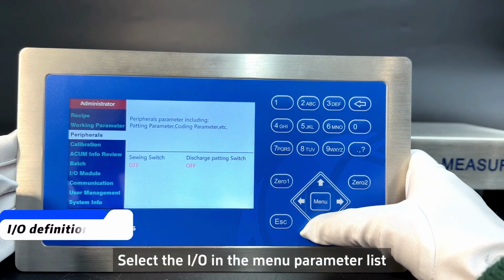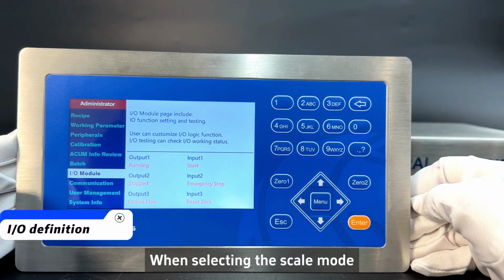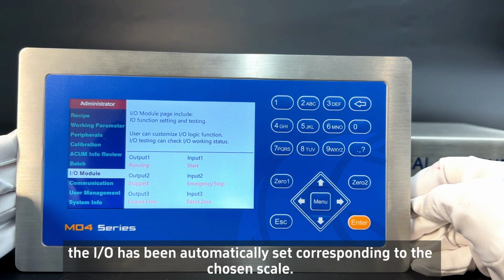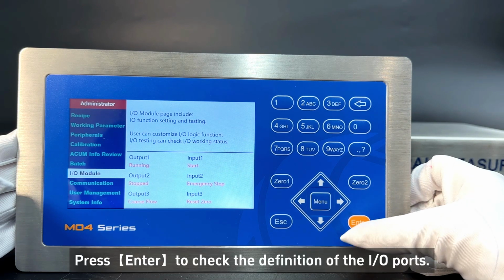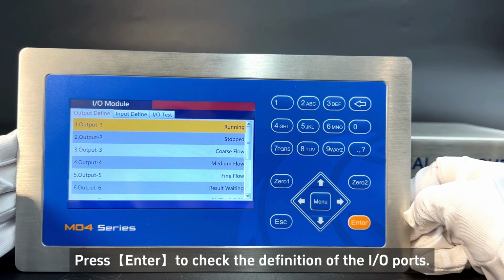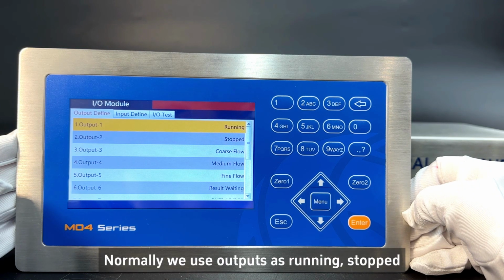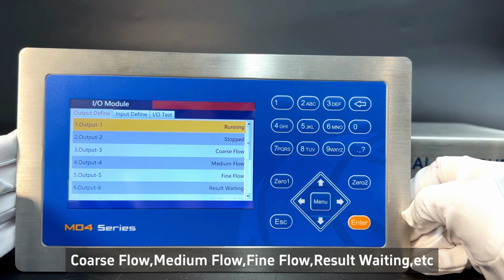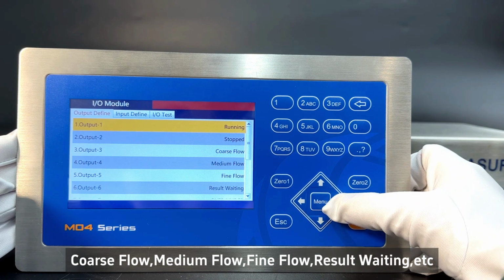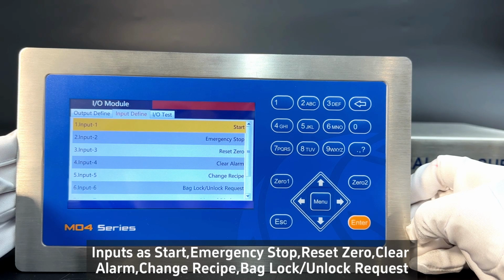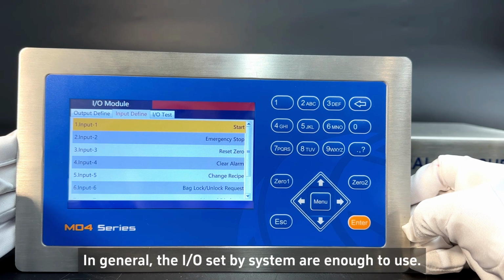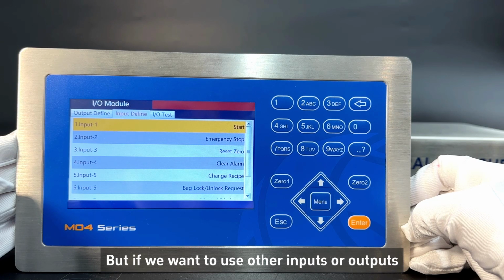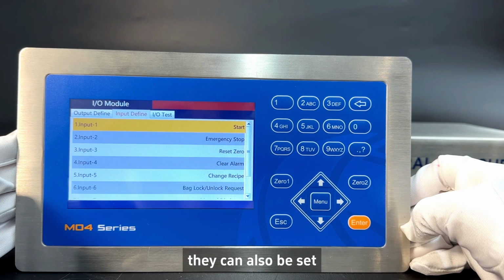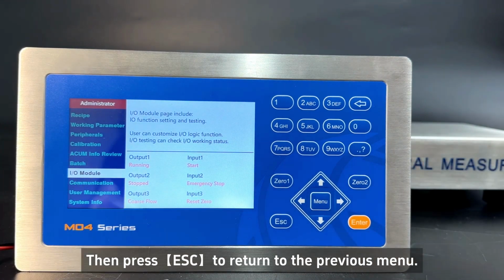Select the I/O in the menu parameter list. When selecting the scale mode, the I/O has been automatically set corresponding to the chosen scale. Press Enter to check the definition of the I/O ports. Normally we use outputs as running, stop, coarse flow, medium flow, fine flow, result waiting, etc. Inputs as start, emergency stop, reset zero, clear alarm, change recipe, bag lock/unlock request. In general, the I/O set by system are enough to use. But if we want to use other inputs or outputs, they can also be set. Then press ESC to return to the previous menu.